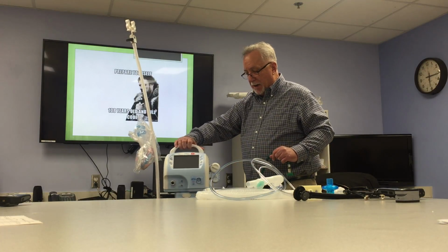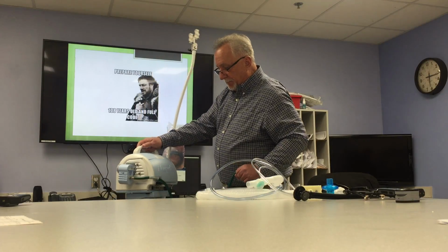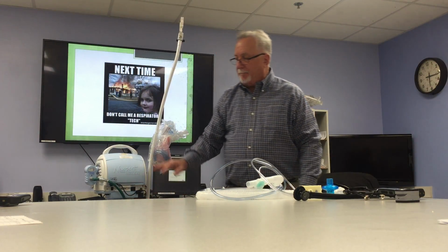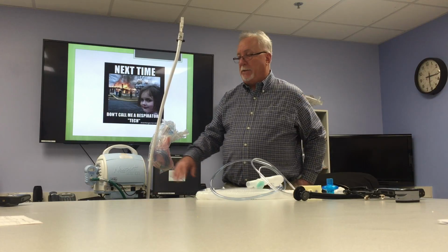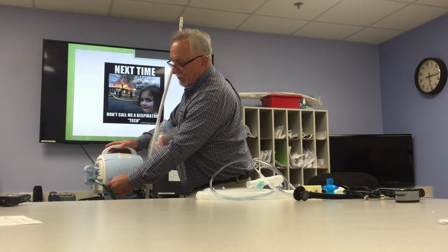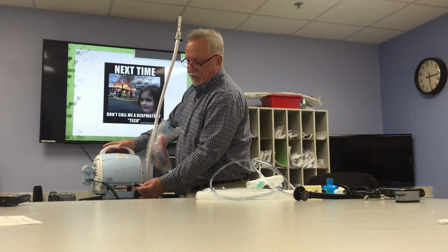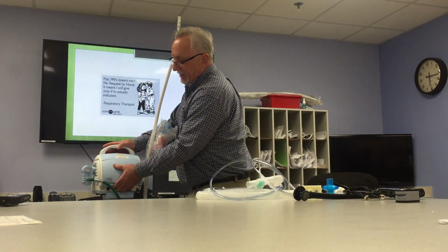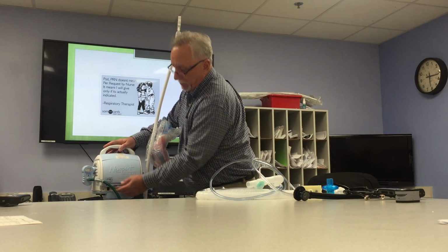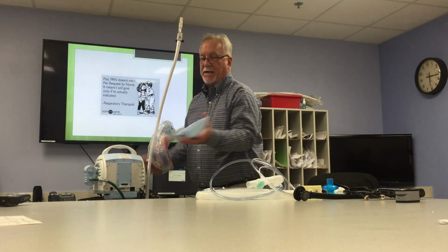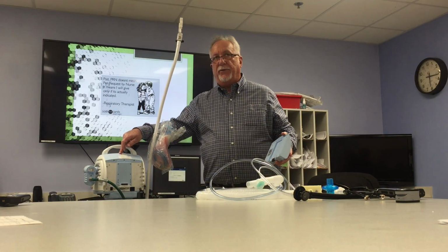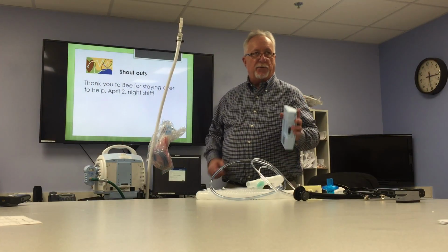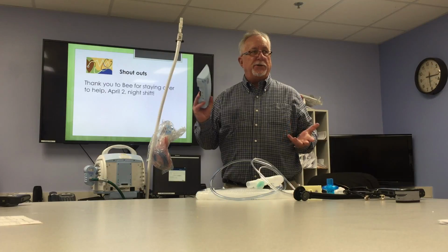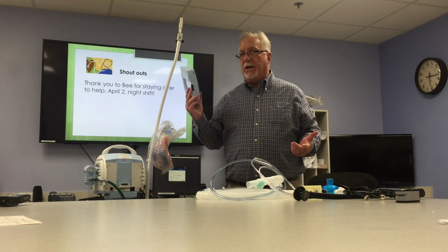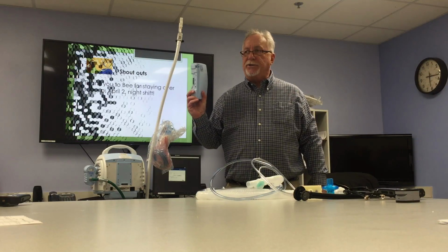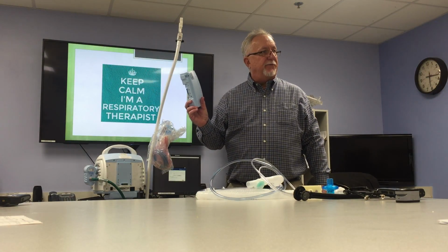The power, the nice thing about it, again, emergency preparedness, is you have an integrated battery that gives you 10 hours. And it attaches, there's a little spring-loaded connection there. You just press it, it pulls it off. The battery is hot swappable. And that slides off. That's a battery. And then there's another 30 minute internal battery. So while it's running, you can go ahead and swap this out and put a new one on. Especially in a situation where you may be running on auxiliary power, you can charge this separate one up and then swap it out while the ventilator is still running.